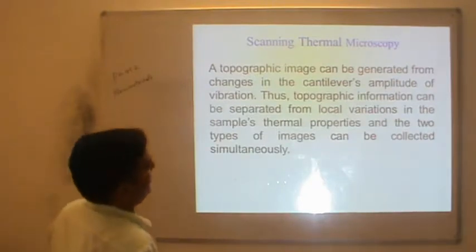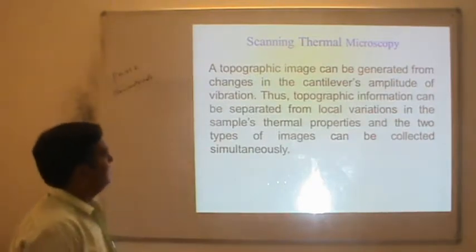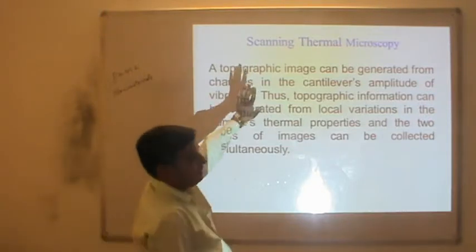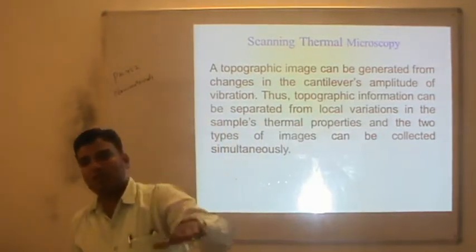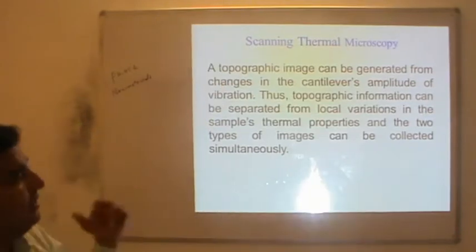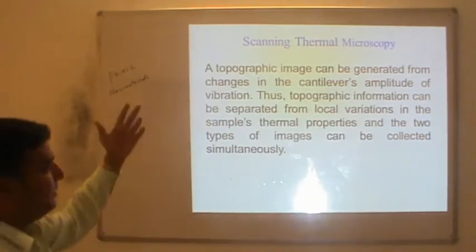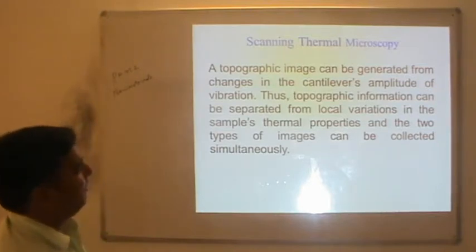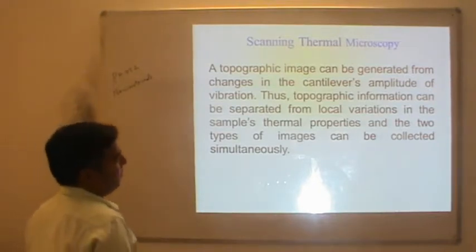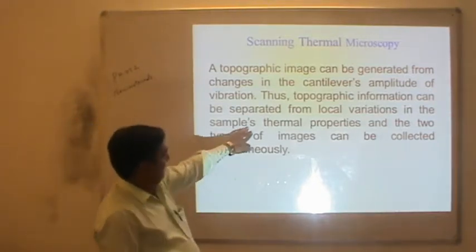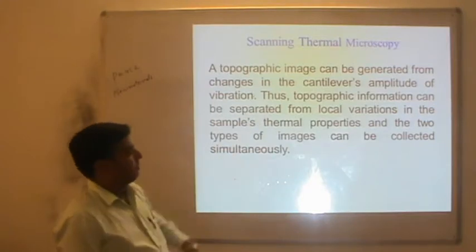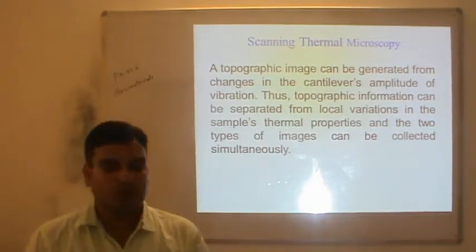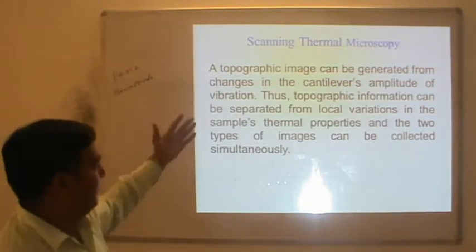A topographic image can be generated from changes in the cantilever's amplitude of vibrations — when it scans the surface, vibrations are observed and preserved as a topographic image of the sample. Topographic information can be separated from local thermal variations in the sample. Thus two types of images can be collected simultaneously: a topographic image and a thermal image.